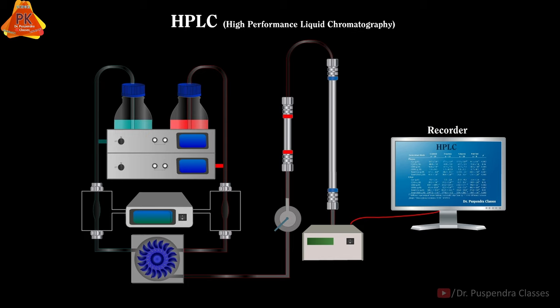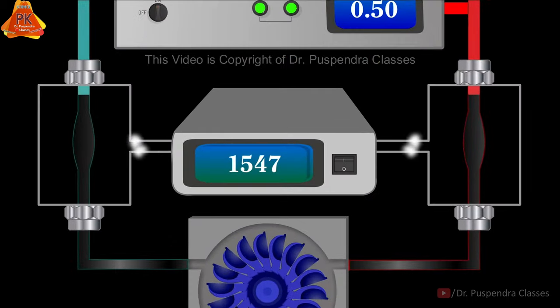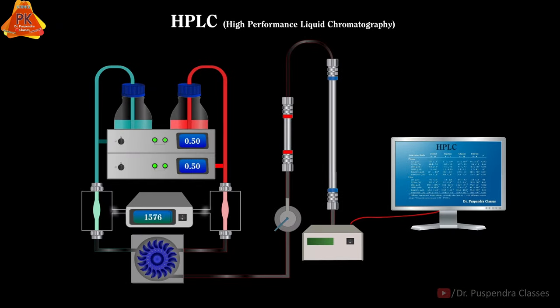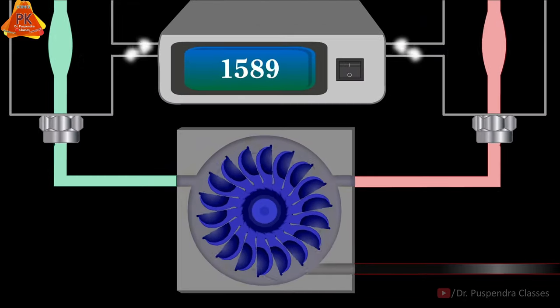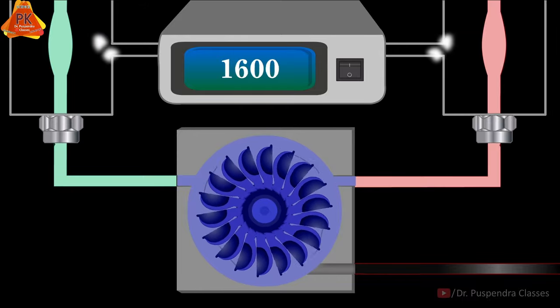After creating the method, the solvent of the mobile phase will be pumped by the HPLC pump from the solvent reservoir towards the degaser. These solvents will come to the degaser, which is attached with a vacuum pump that will create high vacuum. Therefore, any gas or air dissolved in the solvent will be removed online, because this may create problems during elution. After degasing, solvents of the mobile phase will move towards the solvent mixing valve, and mixing of the solvents takes place, which will help to produce a uniform mobile phase.